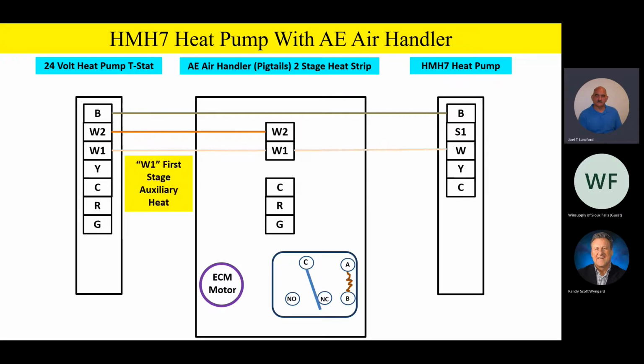W1 from the thermostat is going to go to your first stage auxiliary heat, and if you just have a heat strip in there, W1 will be your first stage auxiliary heat. Now, on some thermostats, I understand Honeywell, they actually designate. For instance, one of our local companies a while back was telling me that most of the Honeywell thermostats, the W1 call is actually an AUX or auxiliary call. So please look at your thermostat, whichever thermostat you're using, and make sure that you know you have the right output for that thing. But W1 on our air handler is going to be our first stage auxiliary heat.